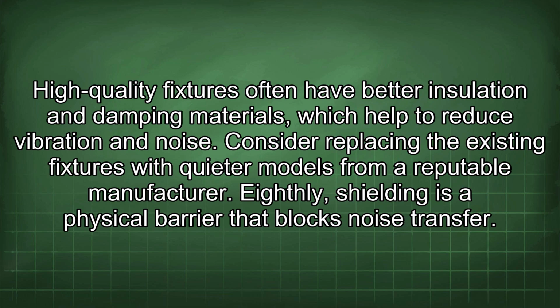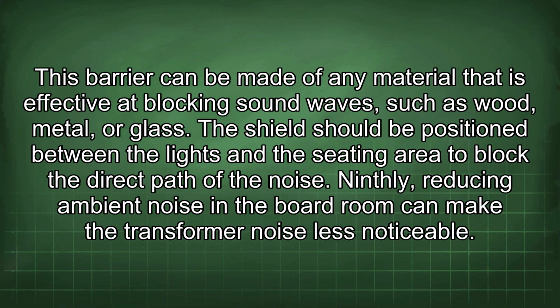Eighthly, shielding is a physical barrier that blocks noise transfer. This barrier can be made of any material that is effective at blocking sound waves, such as wood, metal, or glass. The shield should be positioned between the light and the seating area to block the direct path of the noise. Ninthly, reducing ambient noise in the boardroom can make the transformer noise less noticeable.